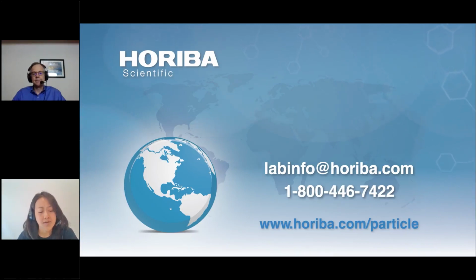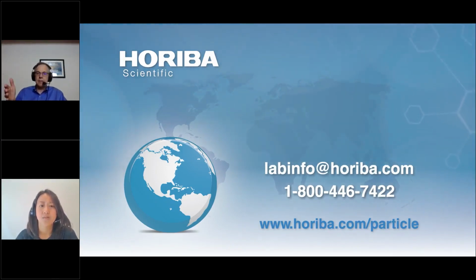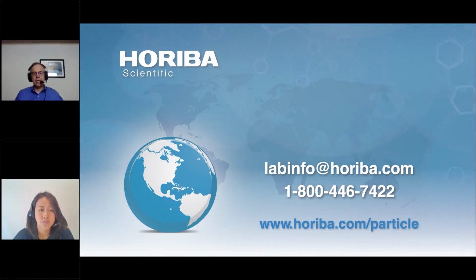That reminds me of a question that came in from the last webinar. When it comes to method development, do you focus on the transmittance percentage first, or do you focus on the refractive index by using the Method Expert? I would try to get close in refractive index, then I would get my trend, and then I would get everything else right, and go back to look at refractive index with the Method Expert. Thank you. And you can definitely recalculate. Yeah, you could do everything and then recalculate all your data later if you find out there's an issue with your old data and you want to find those numbers.